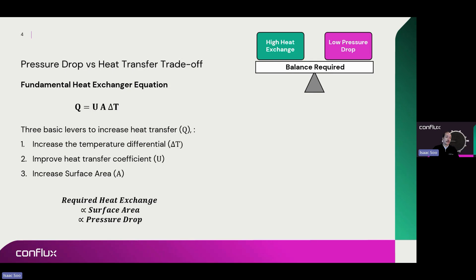So there are a lot of pros to being able to minimize the pressure drop in our heat exchangers, like we've just mentioned: system harmony, efficiency, being able to reduce the weight and size of other components in the system. But there's some key cons as well. As we drive down the pressure drop in our heat exchangers, we might fundamentally need to reduce the amount of surface area or the amount of obstruction that the fluid undergoes. So this can reduce the overall heat rejection of the device. If we want to counteract that effect, we might need to resize the device, say a larger device frontal area. We might need to shorten the flow paths, or we might need to do a combination of that with core density as well.